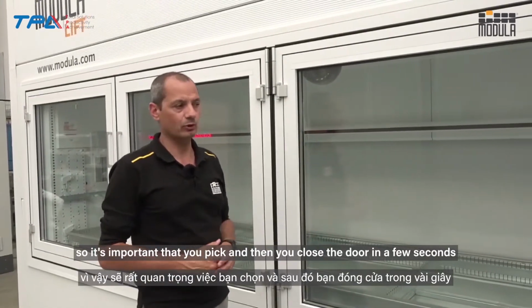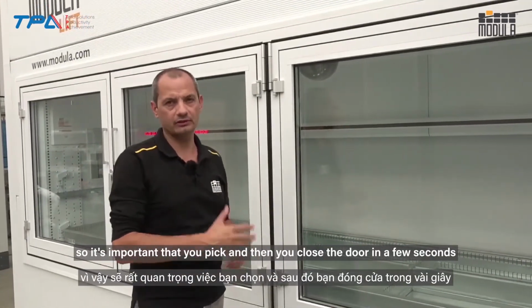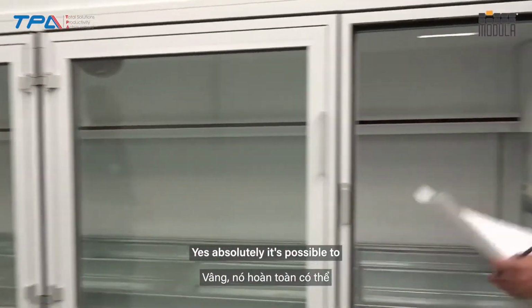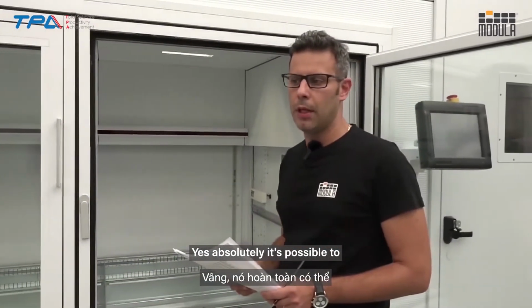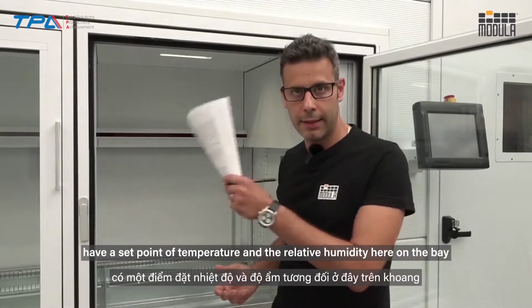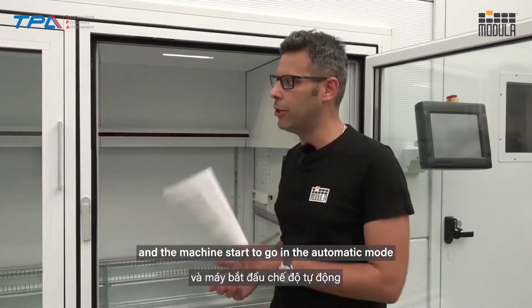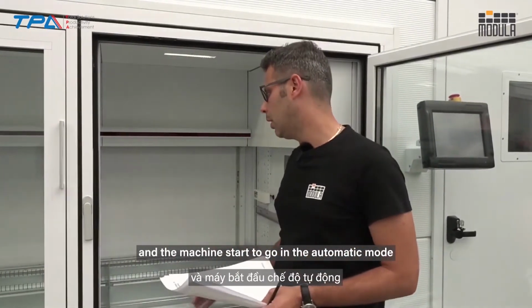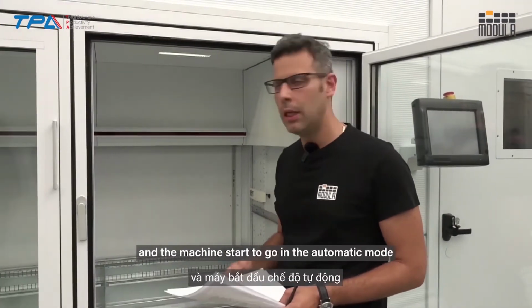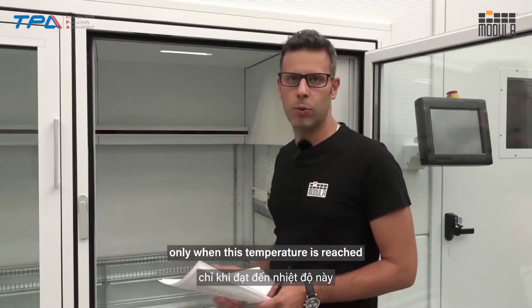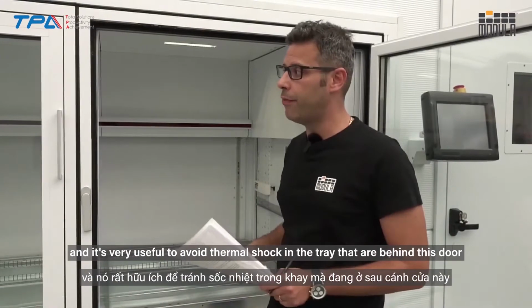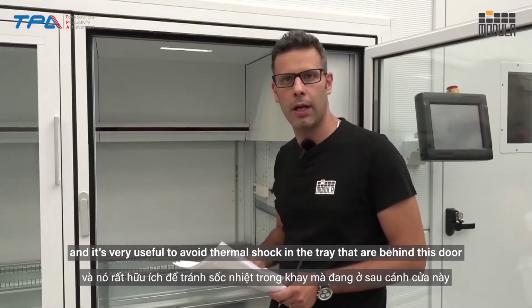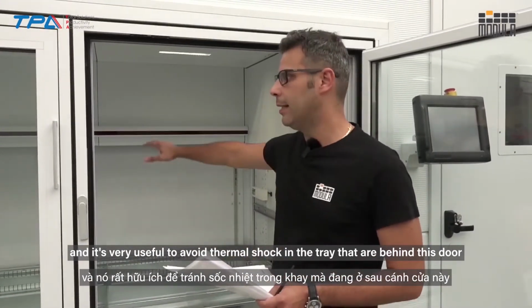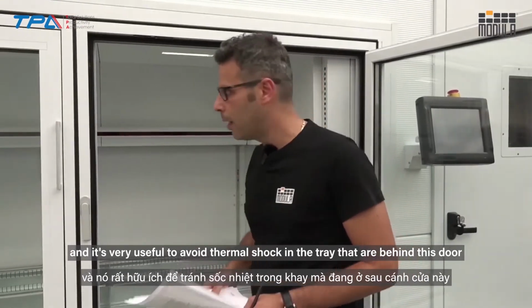So it's important that you pick and then close the door in a few seconds. Yes, absolutely. It's possible to have a set point of temperature and relative humidity here on the bay, and the machine starts to go in automatic mode only when this temperature is reached. It's very useful to avoid thermal shock in the trays that are behind this door.